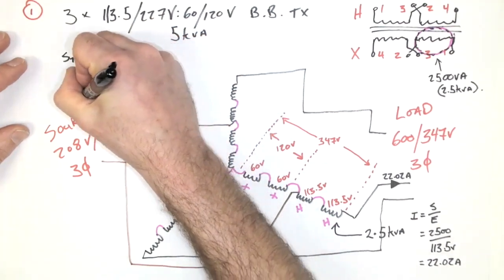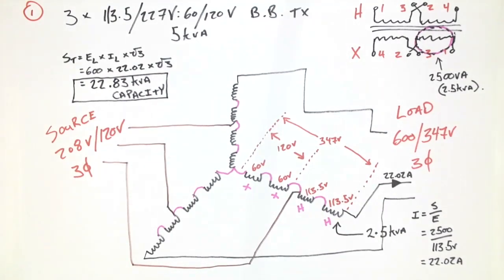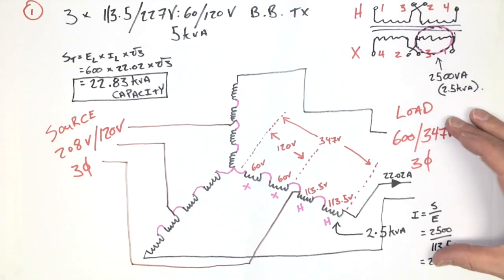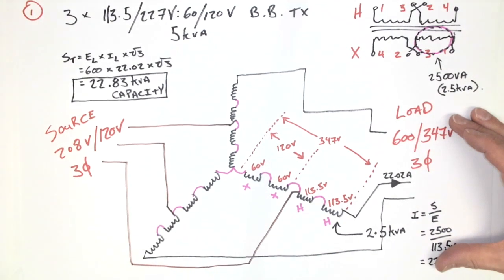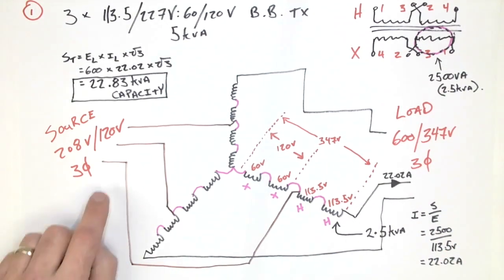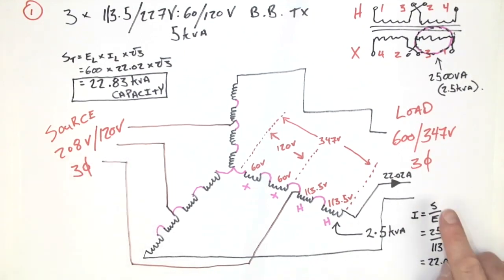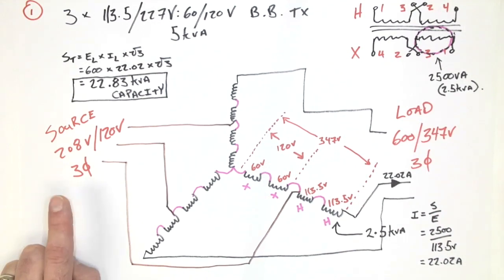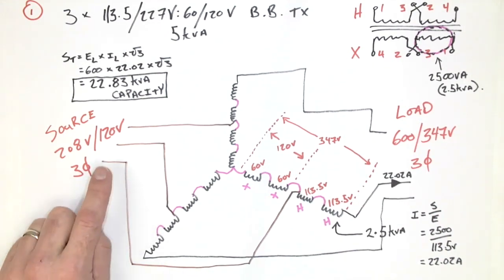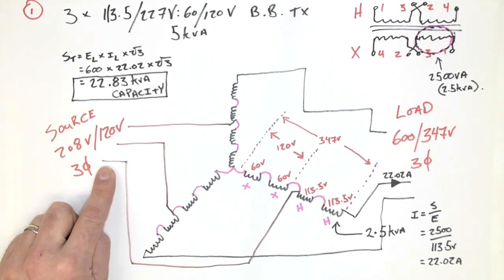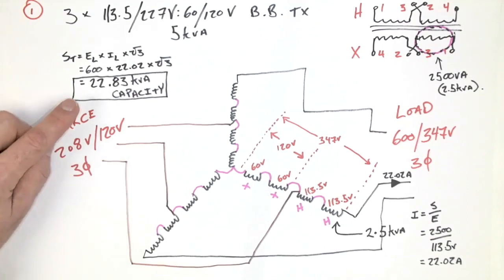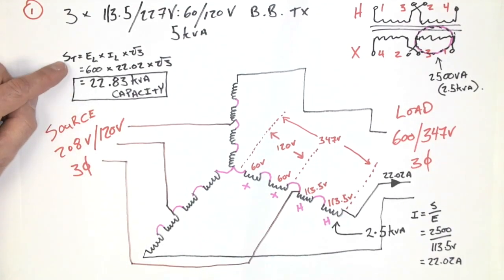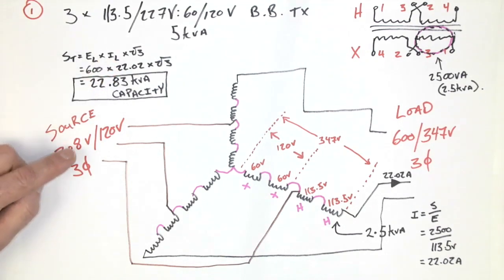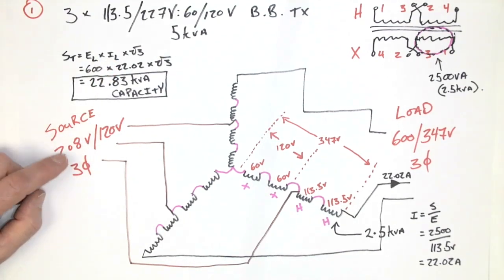This is the safe capacity for this particular transformer bank, with a 600 volt load and 208 volt source. We can drive a 22.8 kVA load. And of course, if we wanted to calculate the equivalent line current on the primary, remember, kVA out equals kVA in. So you could quite easily calculate the primary source current by taking the 22.83 kVA and adjusting our formula to calculate I line on the primary, which would be at the 208 volt line value.